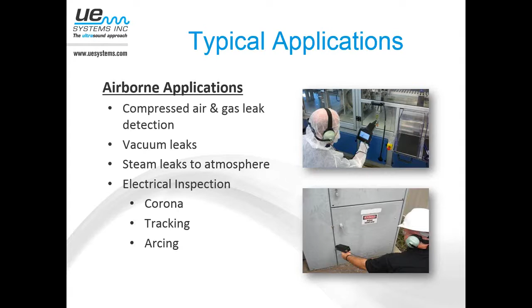Steam leaks out to atmosphere, and electrical inspection, whether that be outside in your substation, in switchgear, enclosed switchgear and motor control centers in your plant. Ultrasound is a quick, accurate way to determine if you have corona, tracking and arcing. Some typical structure-borne applications, the ones I just talked about up here incidentally, were all what we call airborne applications. So we use a scanning module on one of the ultrasonic tools, and these are sounds that travel through the air out into atmosphere, and we can hear them.